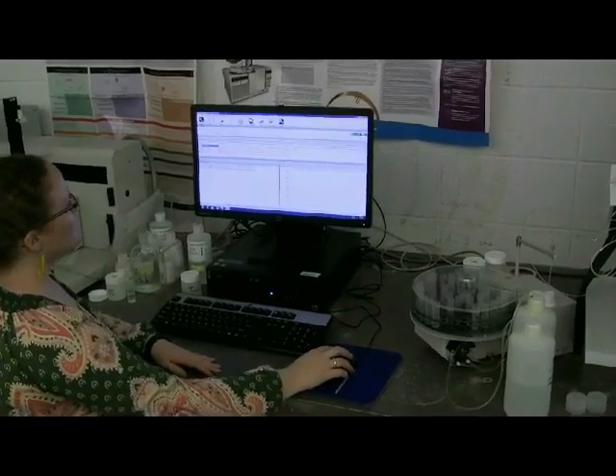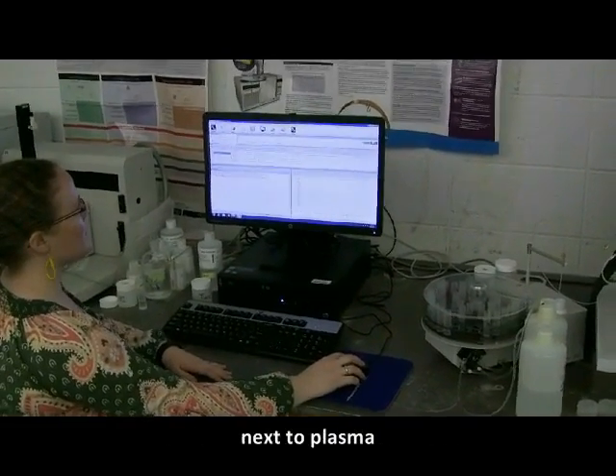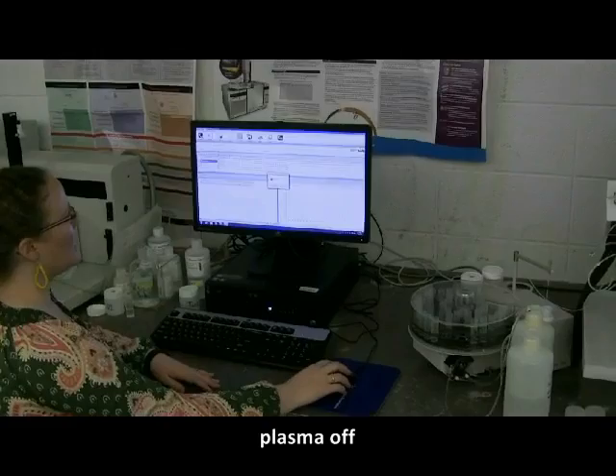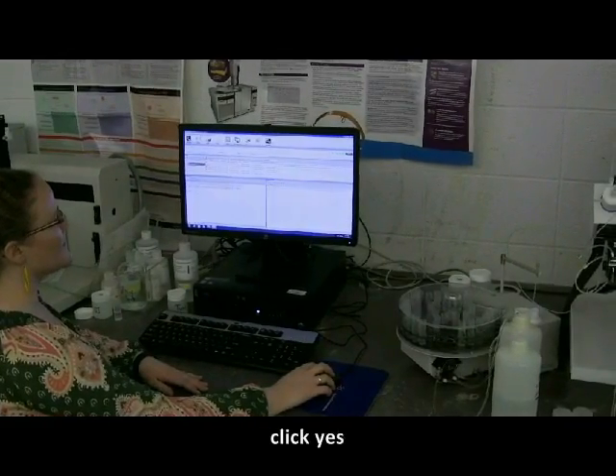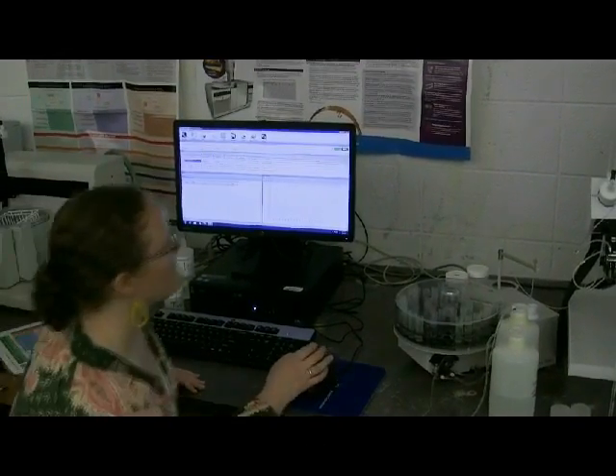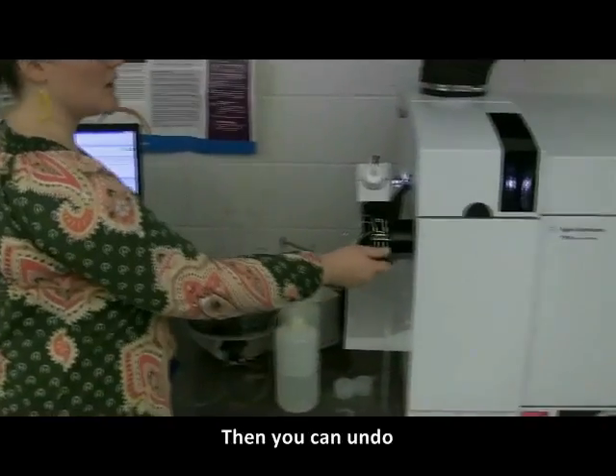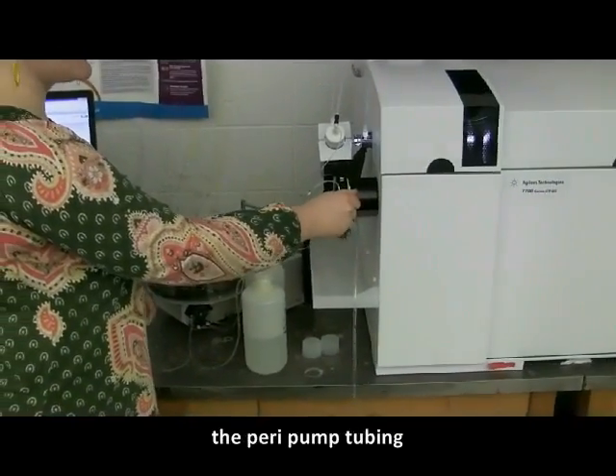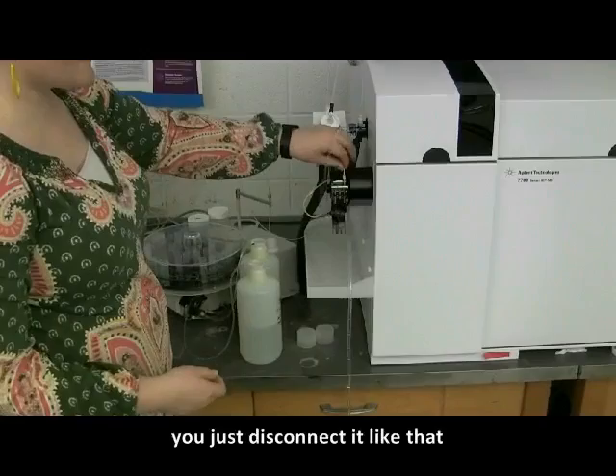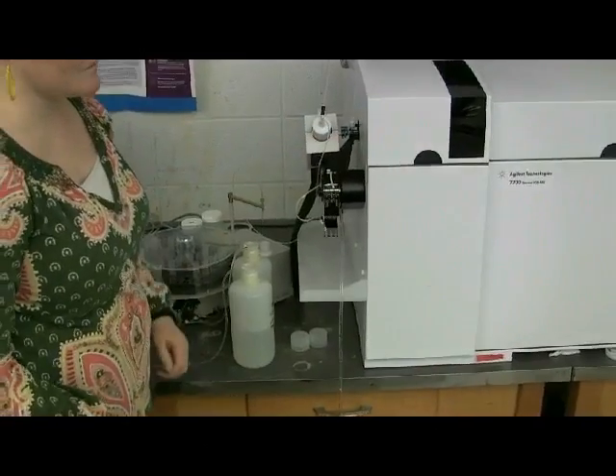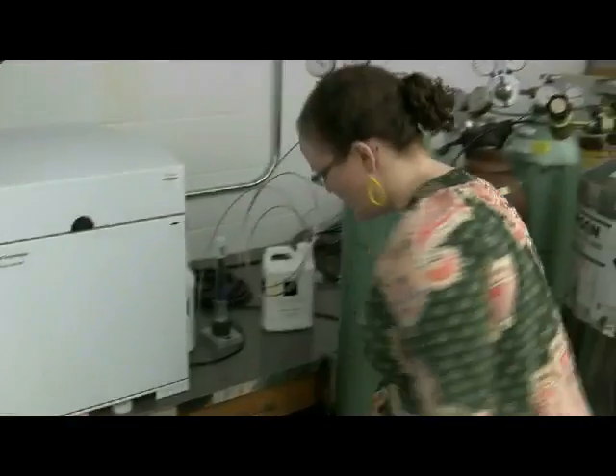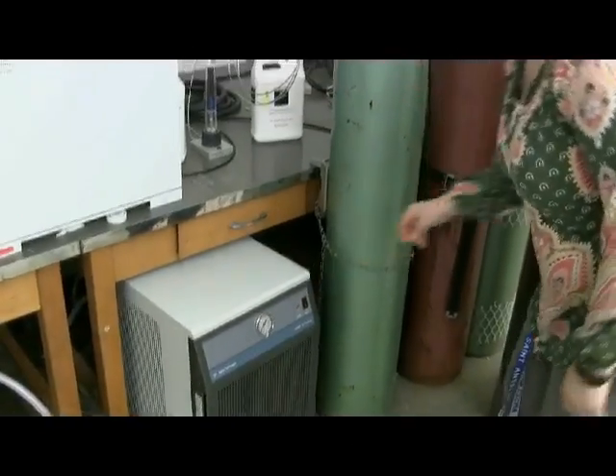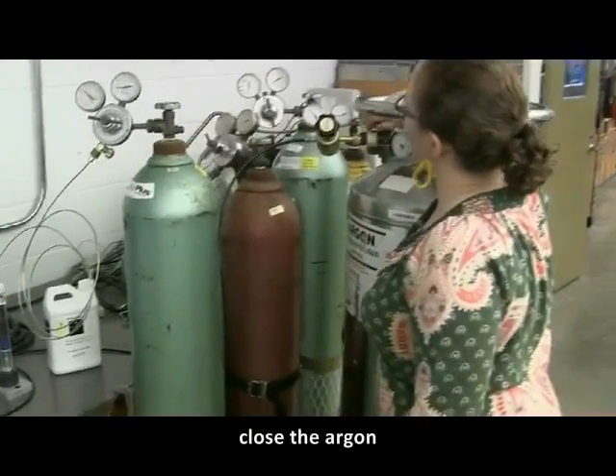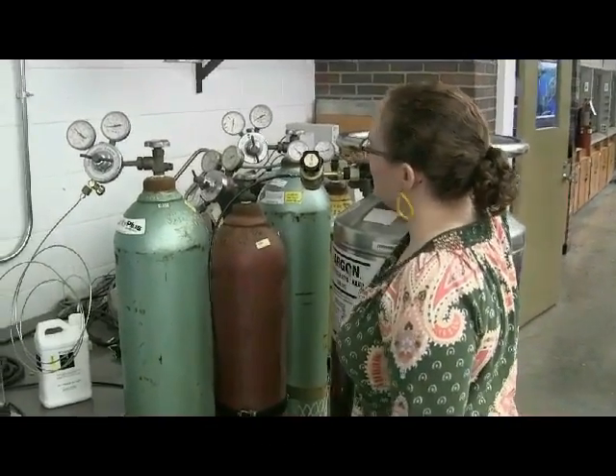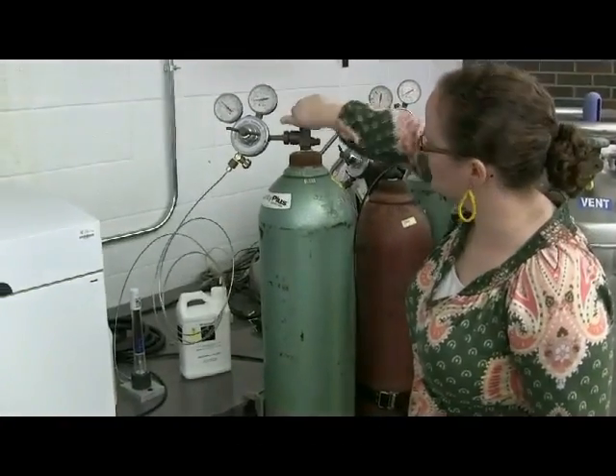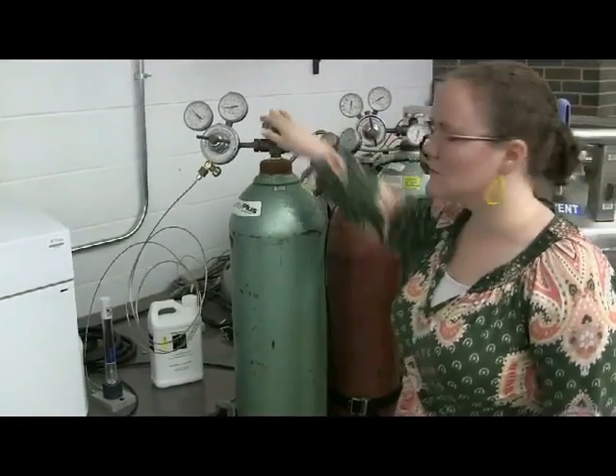Then here, you click on the small black arrow next to plasma. Plasma off. Click yes. Then you can undo the peri pump tubing. You just disconnect it like that. Turn off the chiller. Close the argon. And close the helium. Then you're done.